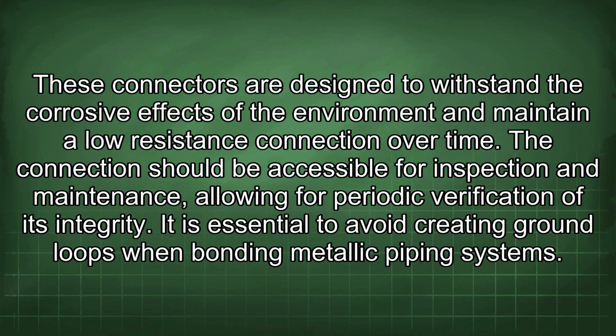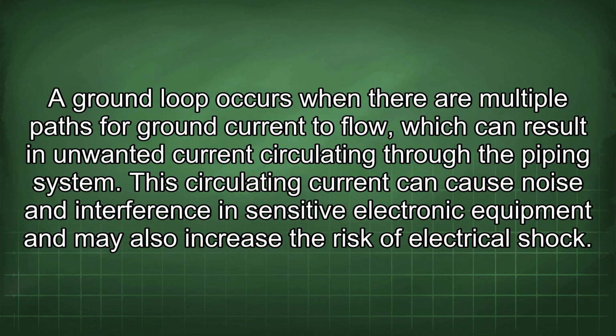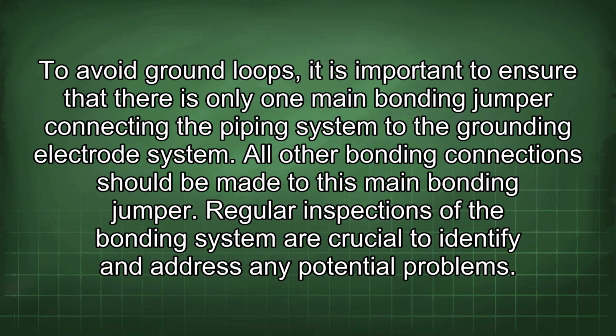It is essential to avoid creating ground loops when bonding metallic piping systems. A ground loop occurs when there are multiple paths for ground current to flow, which can result in unwanted current circulating through the piping system. This circulating current can cause noise and interference in sensitive electronic equipment and may also increase the risk of electrical shock. To avoid ground loops, it is important to ensure that there is only one main bonding jumper connecting the piping system to the grounding electrode system. All other bonding connections should be made to this main bonding jumper.